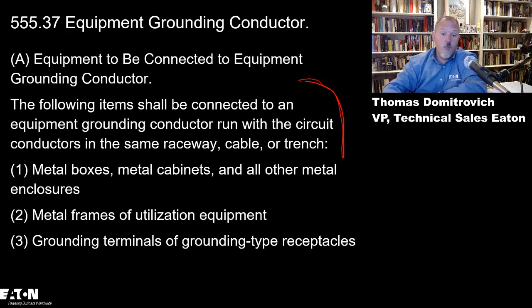All right, I'm just looking at the equipment grounding conductor. 555.37 talks about the EGC. It tells you what has to be connected to an equipment grounding conductor and run, and then it has to be run with the circuit conductors in the same raceway, cable, and trench. It tells us that it has to be an insulated conductor, green with one or more yellow stripes.